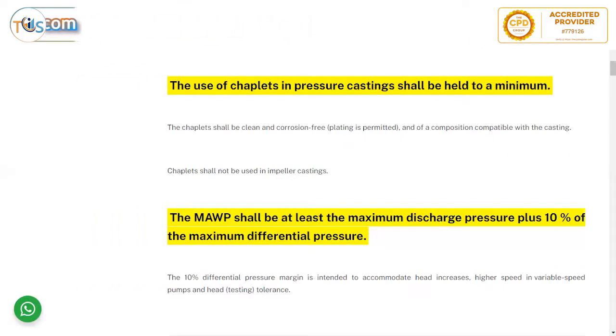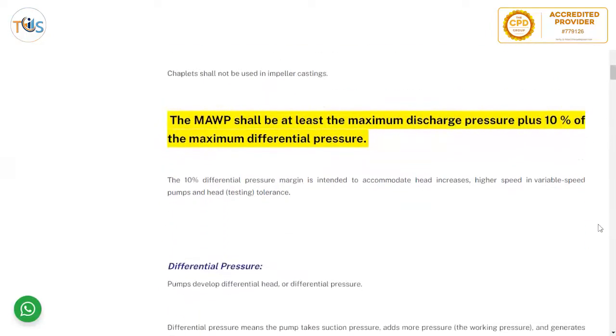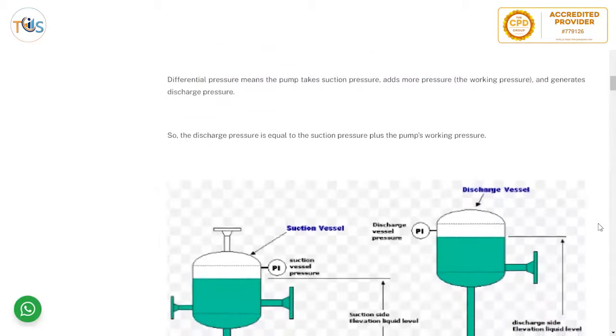The maximum allowable working pressure should be at least the maximum discharge pressure plus 10 percent of the maximum differential pressure. This 10 percent margin is intended to accommodate head increases due to higher speed in variable-speed pumps or head and testing tolerances. Differential pressure means the pump takes suction pressure, adds its working pressure, and generates discharge pressure — so discharge pressure equals suction pressure plus the pump's developed pressure.